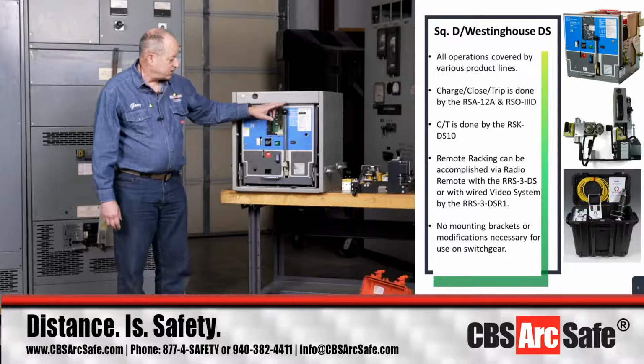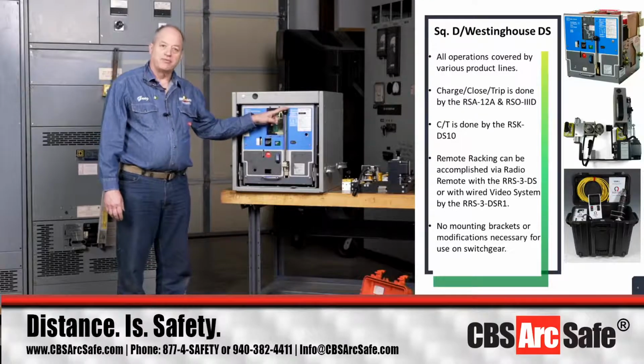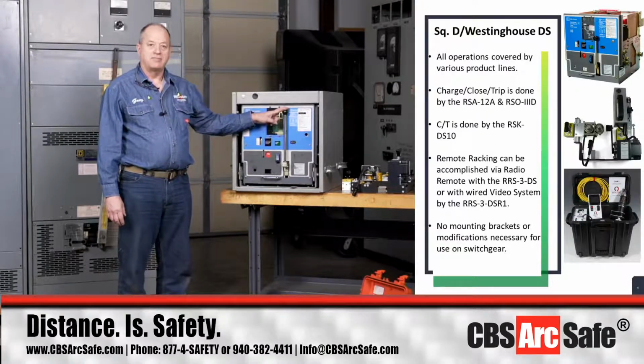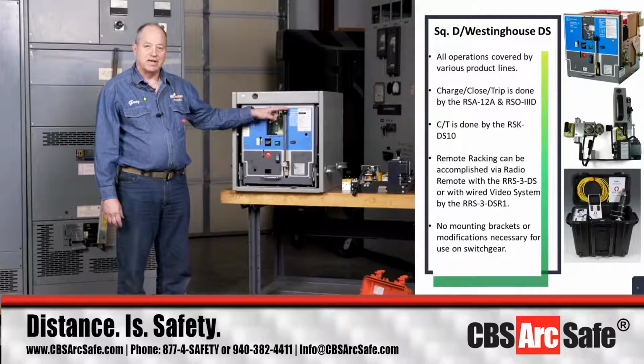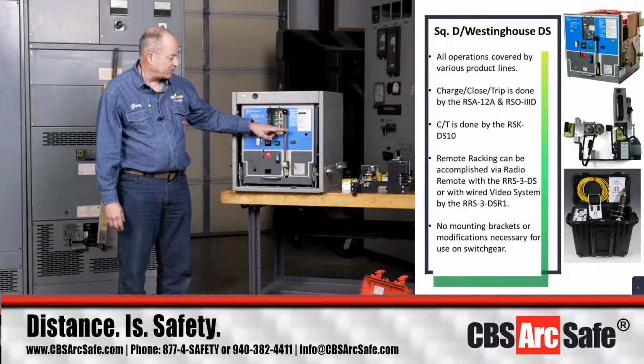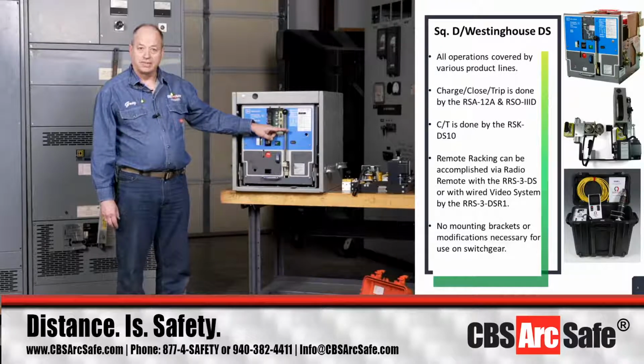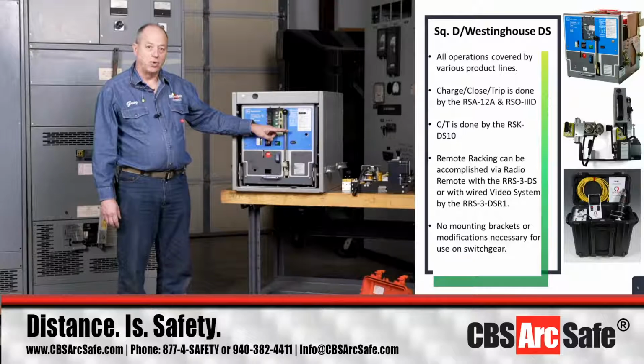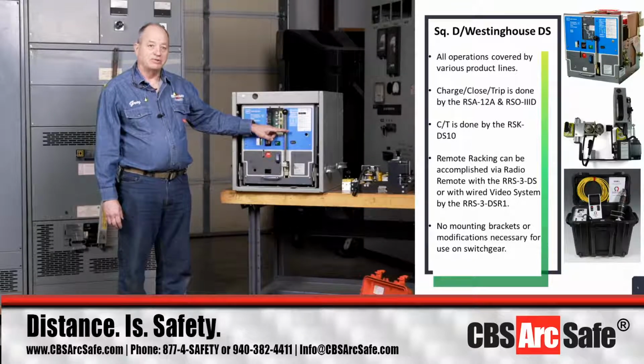One other thing to note: this is the manually operated version of the breaker. The manual operated version has the longer handle like this. If this were an electrically operated version, the handle would be about two-thirds as long. The difference is a manually operated breaker takes one stroke to charge the spring, while an electrically operated breaker takes nine strokes.